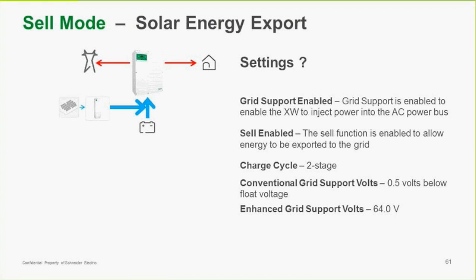Sell mode. So now we're going to sell to the grid. So we have grid support enabled. We have sell enabled. Again, we're at charge cycle 2-stage because we want to move as much power through here. We don't want to delay because we're sitting in float. And we keep providing as much power in sell mode to the grid as we can.